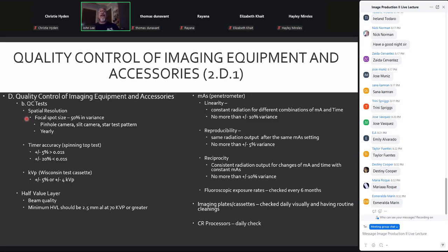KVP needs to be plus or minus 5% or plus or minus 4 kV in its margin of error. And there's a special cassette that is utilized for the KVP QC test. That's called the Wisconsin test cassette. Remember that half value layer is an indicator of beam quality. For a new system, anything operating at over 70 kV or with the potential to be operated at over 70 kV needs to have at least 2.5 millimeters of aluminum equivalent.